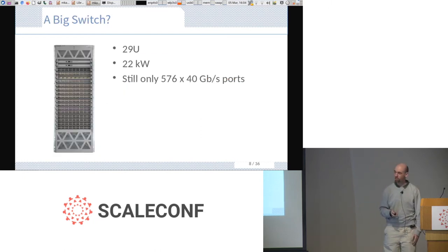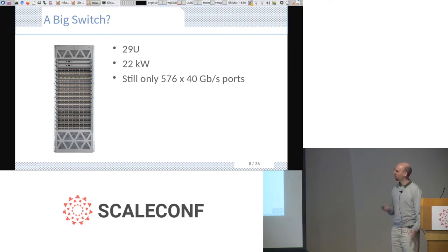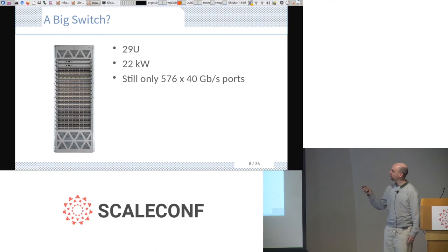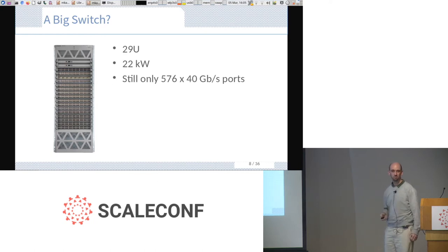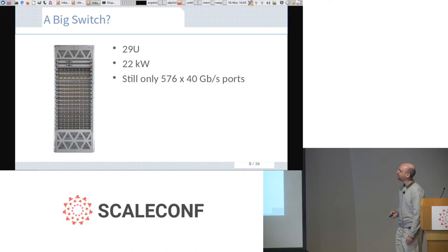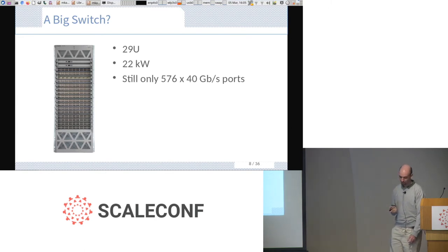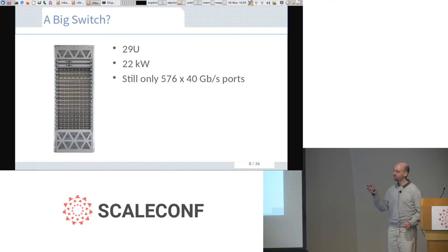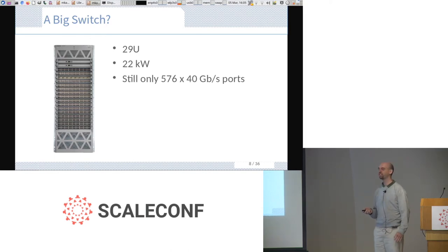Could we just buy a very big switch? That's an Arista switch there — Cisco will sell you something similar. It's 29 rack units and full rack width. It draws 22 kilowatts, which won't fly since our budget per rack is about 10 kilowatts. It still doesn't reach our 648 ports. And imagine running 576 cables into one rack — it would be a complete utter disaster.